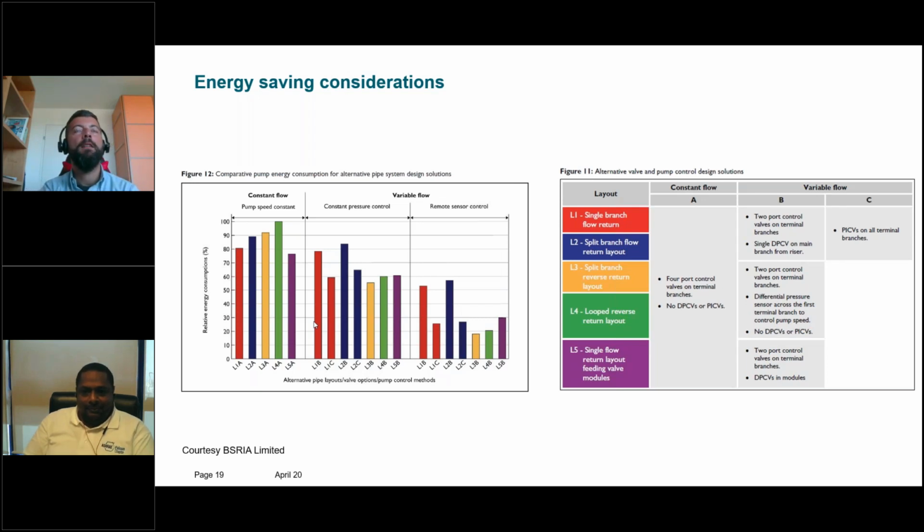That is, I think, from my end. Yeah. So, if you have an answer on this? Yeah, I just wanted to add something on it. The alarm possibility is crucial to that, because if you don't notice that you are violating the delta T and you find out too late, then the penalty could be different. So having the possibility to detect any deviation in the behavior or the performance of the system through alarms or real-time alarms is important. And a mechanical PICV, unfortunately, cannot do that. Okay. Yep. Right. Thank you, Luca.